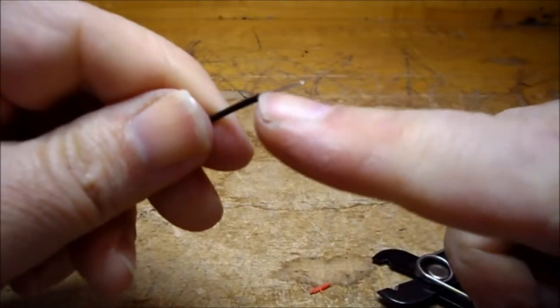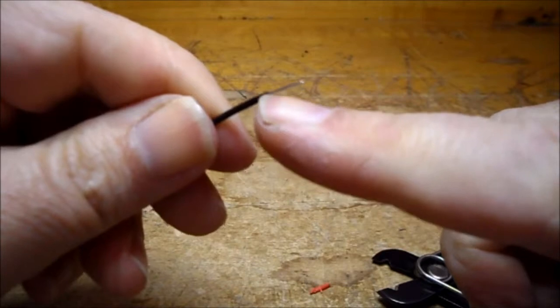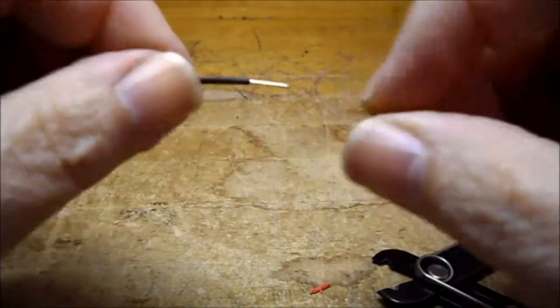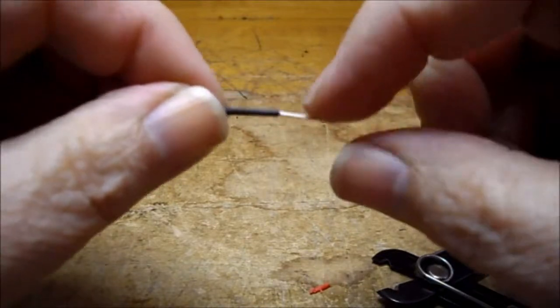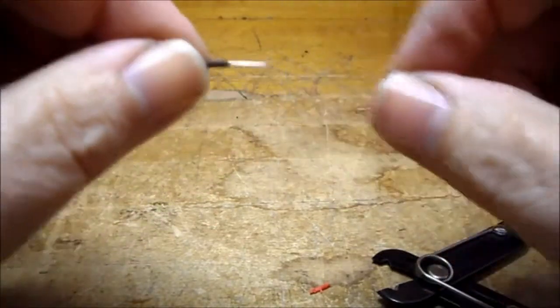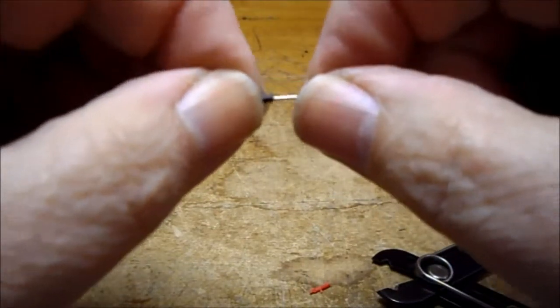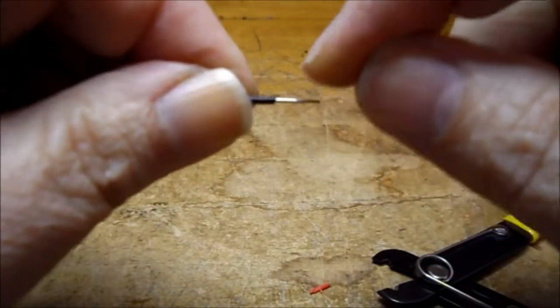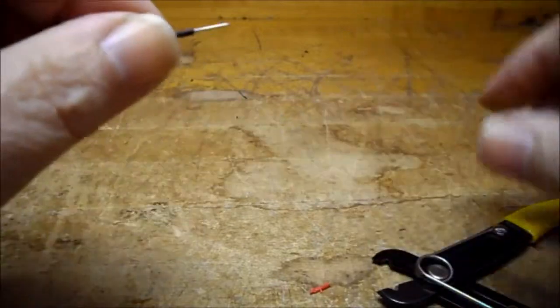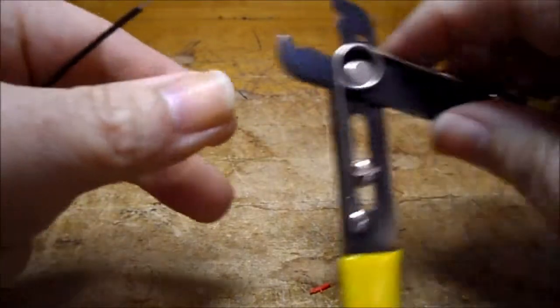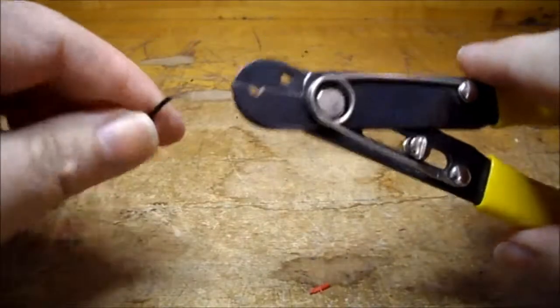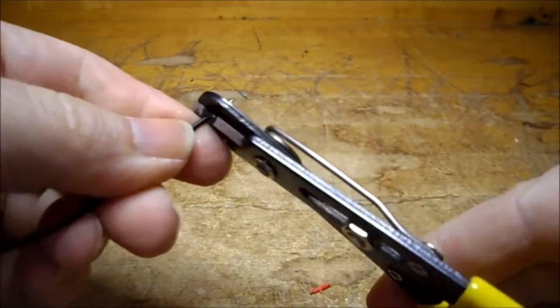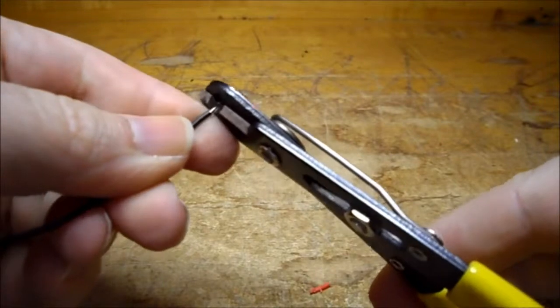If you nick the wire, what's going to happen is it's going to cause a weak point there. As you bend these wires back and forth, where is it going to break? At the weak point. So it's very important that when you adjust these wire strippers, you adjust it so that the wire when it fits in there can slide back and forth fairly easily.